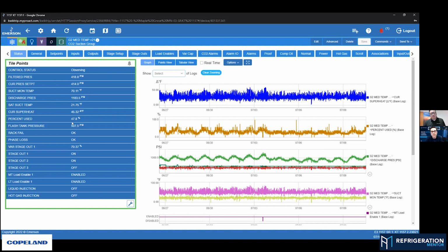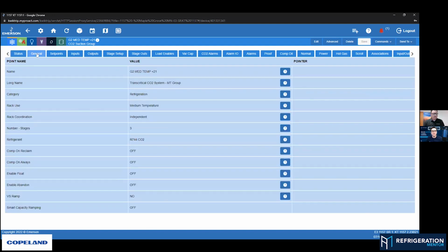Yeah certainly. Like I was saying earlier, the E3 is very similar to the E2 in the way our tabs are laid out within the applications. As you go through, setting up this CO2 suction group for the first time, you're clicking through tabs to tell it how many compressors you have, what your set point is, and things like that. The most important thing to do on an E3 is make sure you click edit at the top of the screen - you'll find out pretty quickly that you can't change anything if you haven't clicked edit. It's a little feature to stop inadvertent changes.